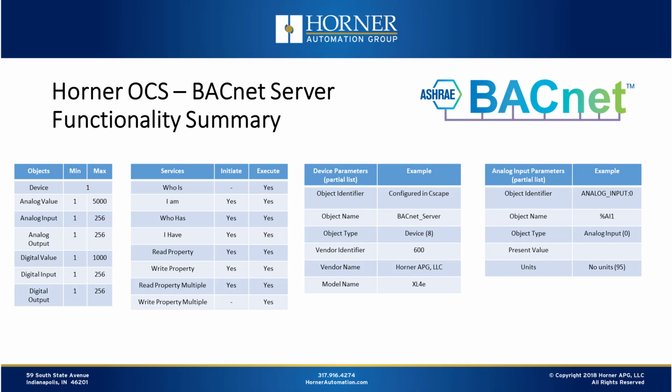So what that means is that an OEM or a machine builder who is, let's say, building chillers that they are selling into a market where BACnet is an important protocol for their customers, a chiller manufacturer would have the opportunity to pick and choose the objects that they need among those listed in order to provide the data and the interface needed to monitor and control a chiller. So that could be anywhere from just a few points with just a few objects, or it could be very extensive if that was desired.